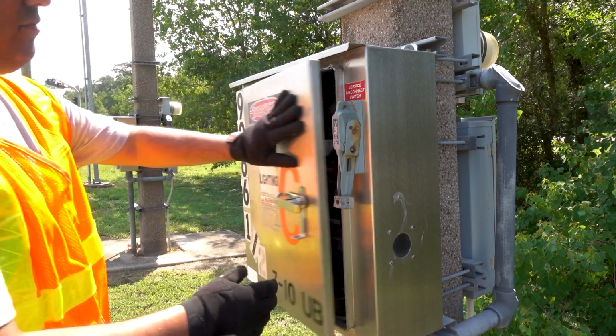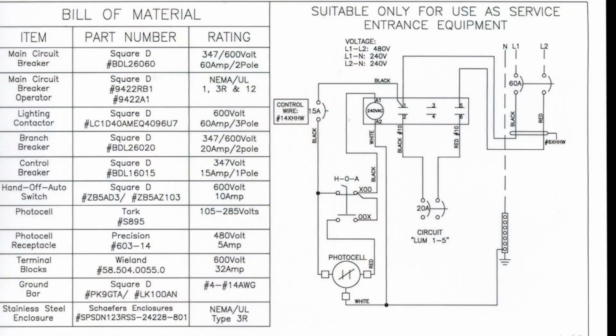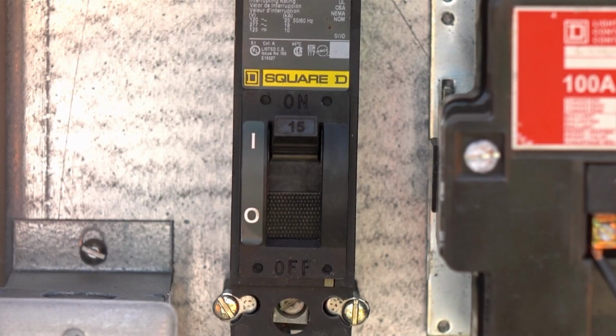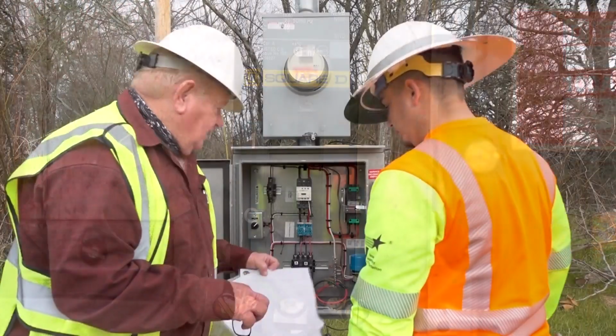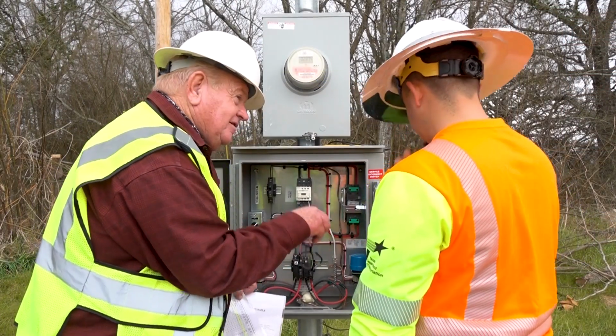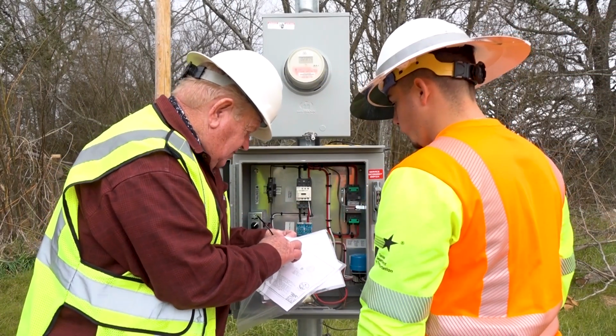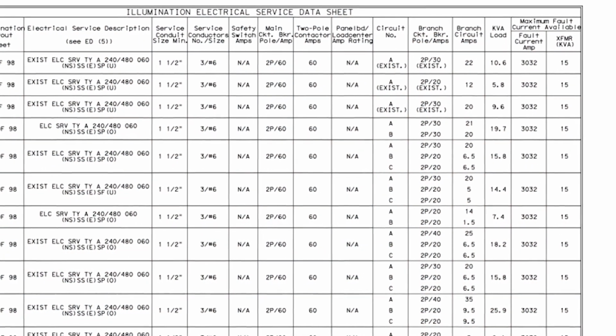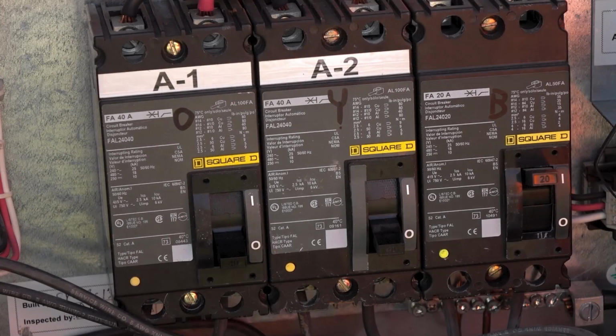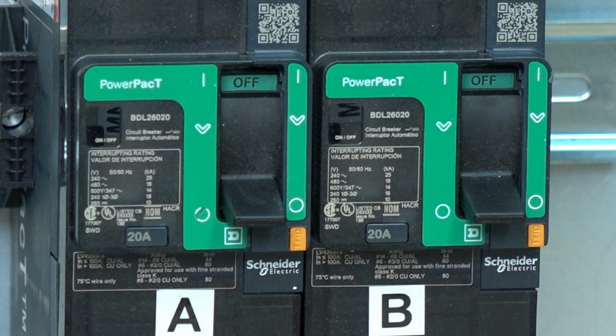The inspector should review the plan sheets for accuracy. Ampere rating of each branch circuit breaker and the load served should be confirmed by a review of the service line's drawing and comparing to what has been installed in the field. Along with the branch breakers, there should also be a single-pole 15-amp breaker for the control circuit. The ampere rating and number of branch circuit breakers installed in the service should be confirmed by visual inspection and by referencing the electrical service data chart in the construction plans. Each branch circuit breaker must be labeled with the load served by that breaker.